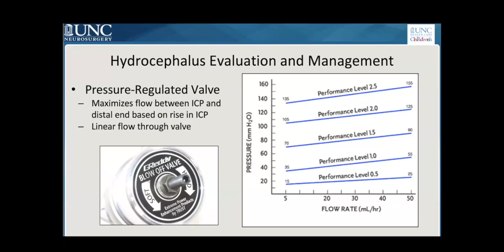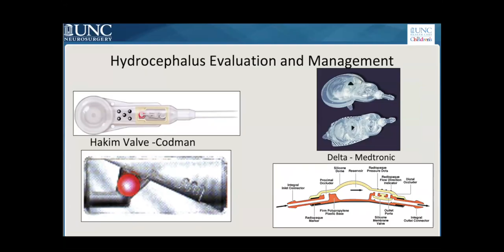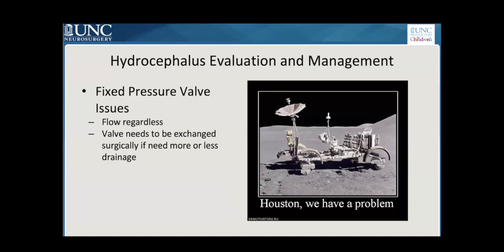There's all kinds of styles of these, and these are just some examples of that. And so these really come down to the people that put them in and where they get put in, and there's not really a benefit of one over the other. So fixed pressure valves have an issue in that they will continue to flow regardless. So if you put, say, a medium pressure valve in, it'll continue to drain at medium pressure. But if you need higher or lower pressure because you're over or under draining, then you've got to go back to the operating room. You've got to remove that shunt valve and put in a new one. So obviously you're exposing these children to more anesthesia, more surgery, and more risk.